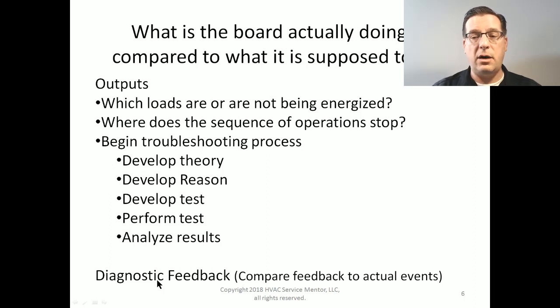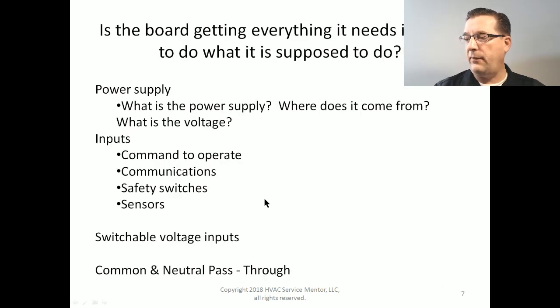So that would be a new starting point, and that modifies our troubleshooting process just a little bit, because I have told you before that you begin your troubleshooting with usually a voltage test at a load or a terminal endpoint. Well, in the case of, say, I'm getting a pressure switch fault or a limit fault or something like that, you need to start there and verify whether or not that fault actually exists. And that can help speed up troubleshooting very quickly.